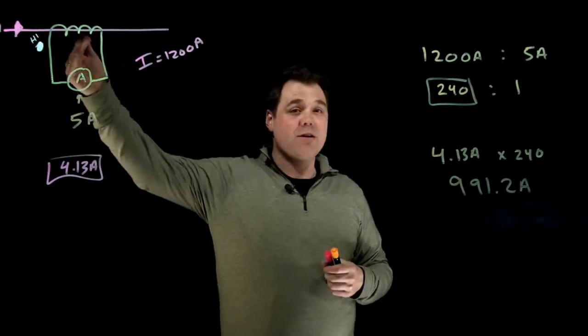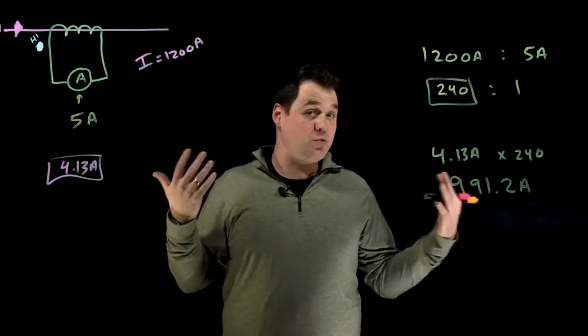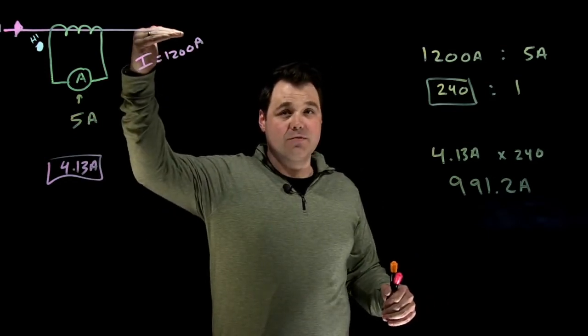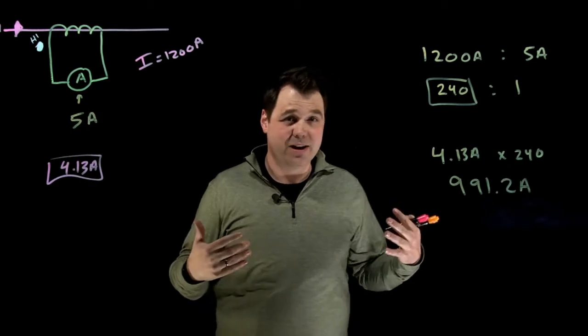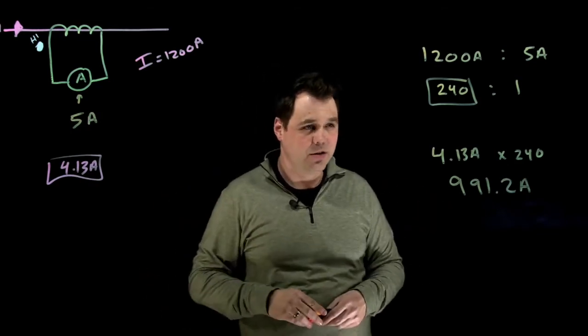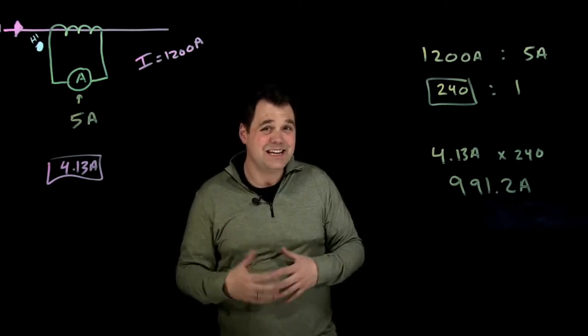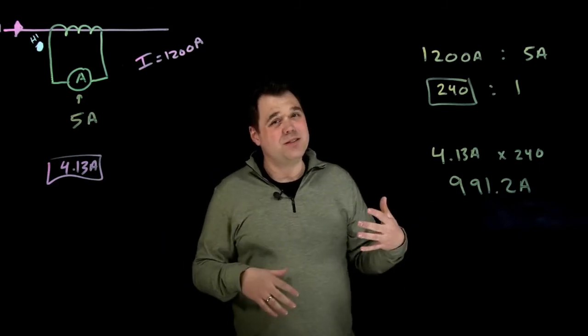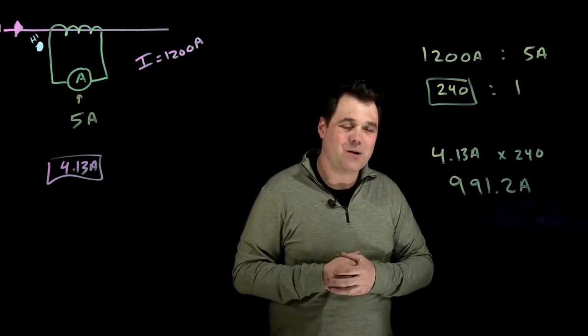And keep in mind, as the primary current goes up, just like a transformer, the secondary current goes up. So it's rated for if there's 1200 amps flowing on the primary, five amps flowing on the secondary. That's how that rating works. They are proportional to each other. That's great. That would be how you would do a calculation with a CT. And of course, I'm going to link another video at the end that has some more CT and PT examples. So keep a look out for that.